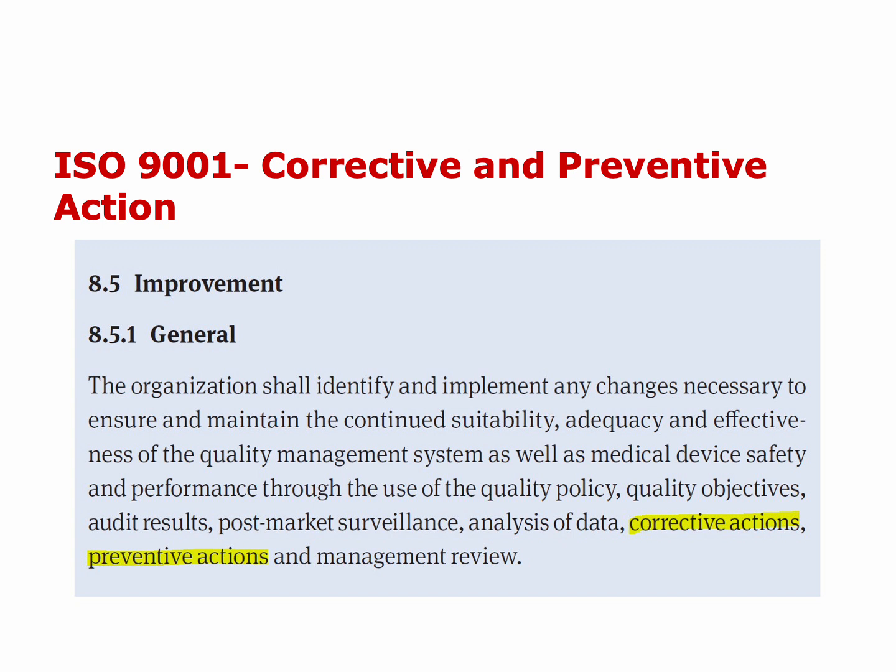When we talk about post-marketing, it means that we are not just going to look into any safety issues or potential issues just before going to the market. We will also need to look into those probabilities of having any patient experiencing any untoward medical occurrence using our products after having the product, or here the device, on the market.